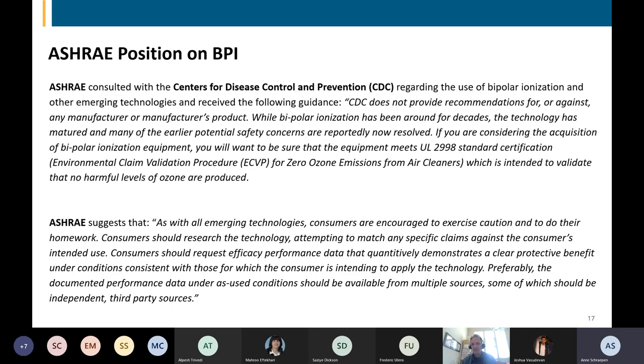They say that if you are considering the acquisition of bipolar ionization equipment, you will want to be sure that the equipment meets UL2998 standard certification, which we talked about, which is intended to validate that no harmful levels of ozone product are produced. They also went on to suggest that, as with all emerging technology, consumers are encouraged to exercise caution and do their homework. Consumers should research the technology, attempting to match any specific claims against the consumer's intended use.